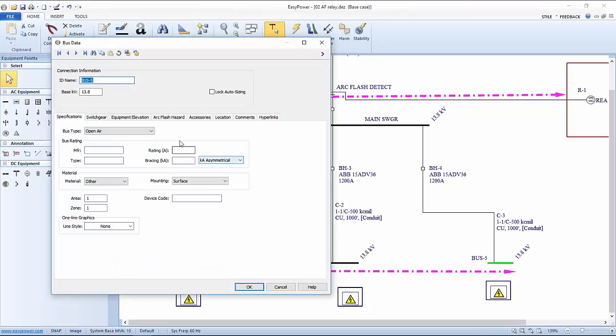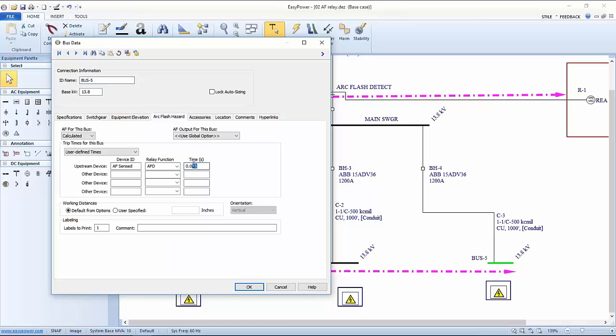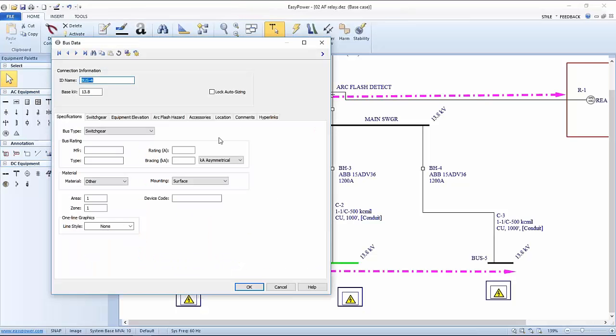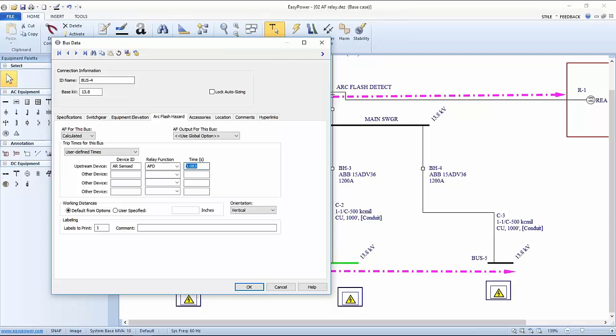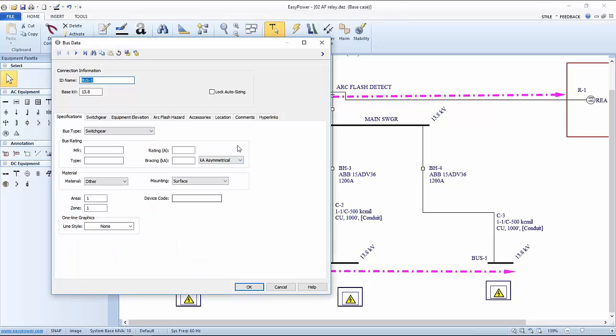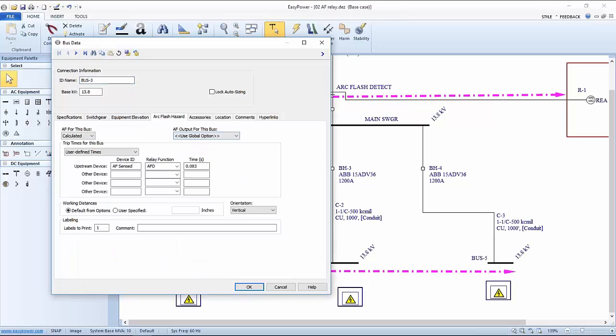The advantage of an Arc Flash Detection system is it can be very fast. The one downstream, the sensor has the ability to determine individual buses. Let's go ahead and make it 12 milliseconds. I guess I need to stay within the rules. These numbers are not arbitrary by any means. They are a function of how I've connected this up and how my control system is reacting to the specific signal. I need to be more specific when I'm looking at the system, what's going to actually take place.